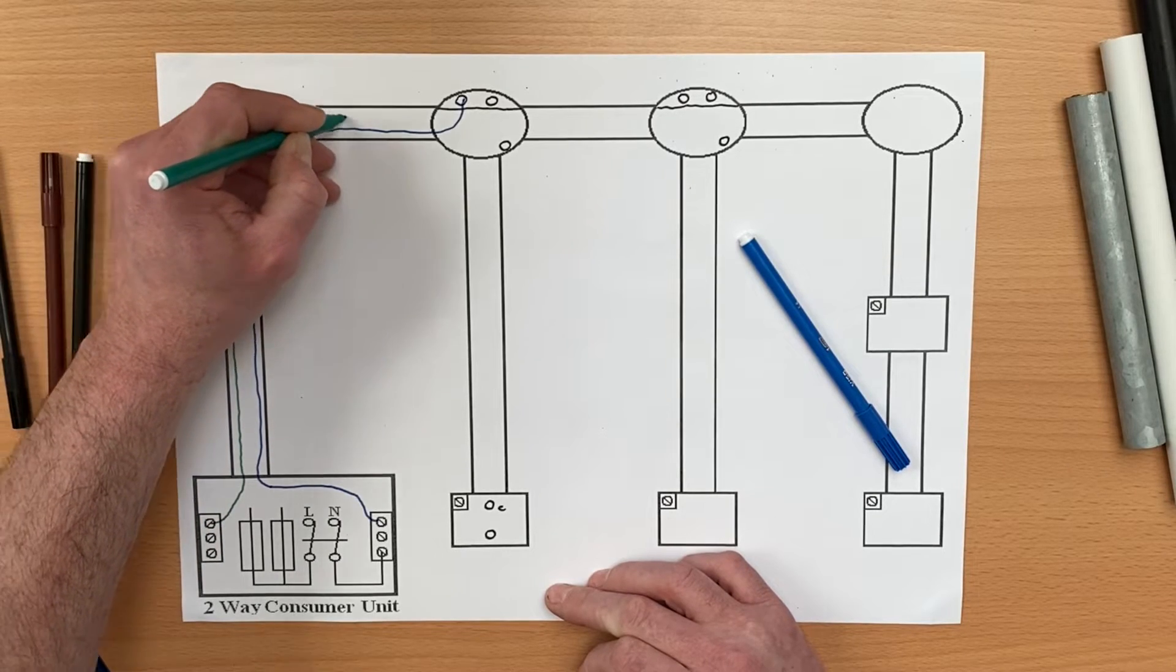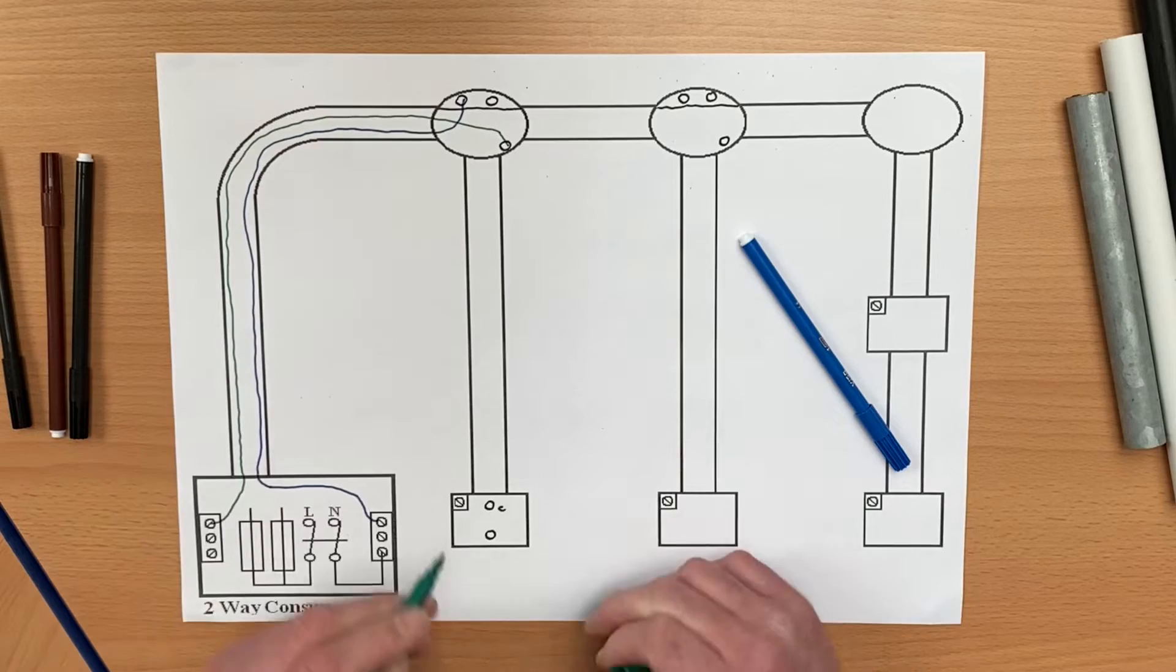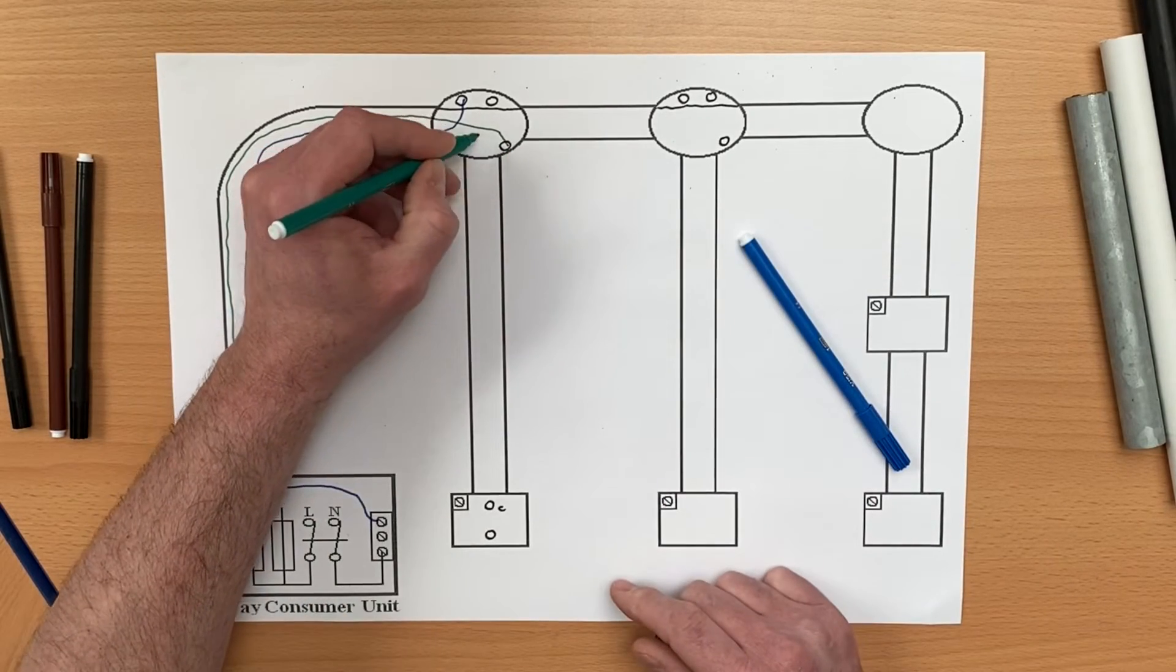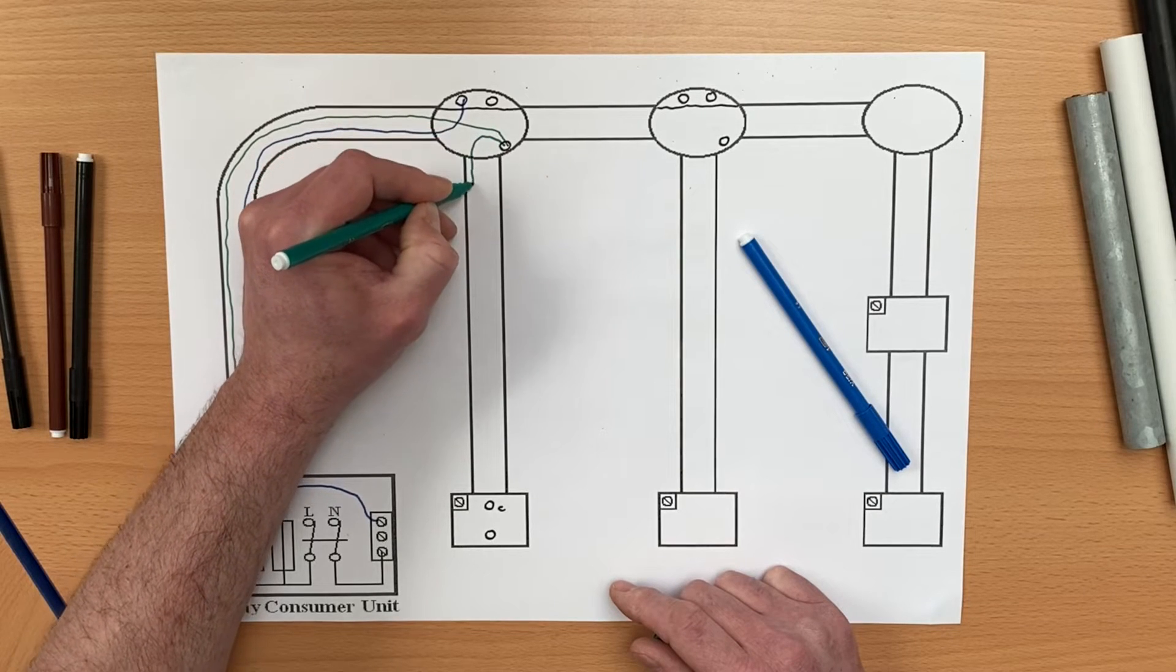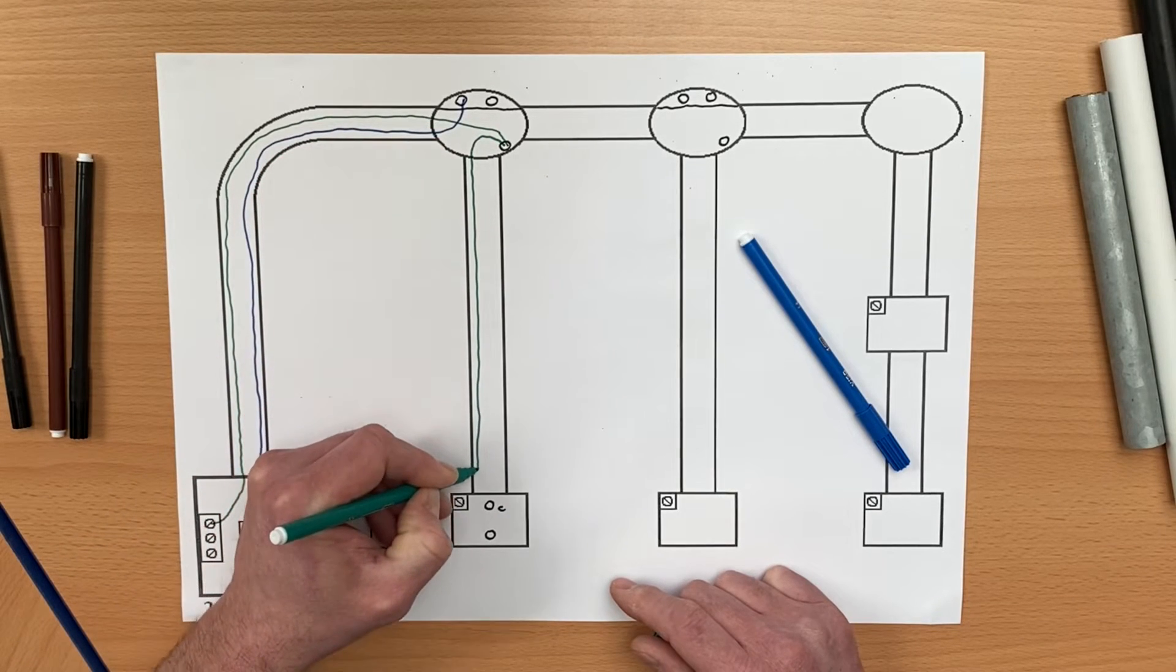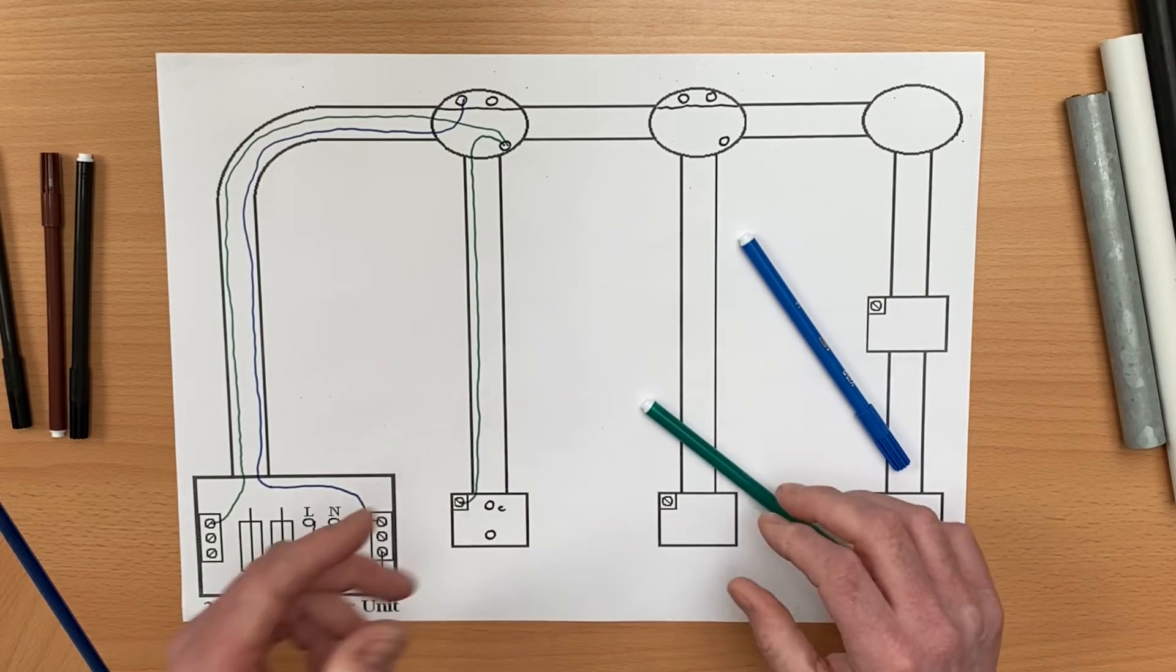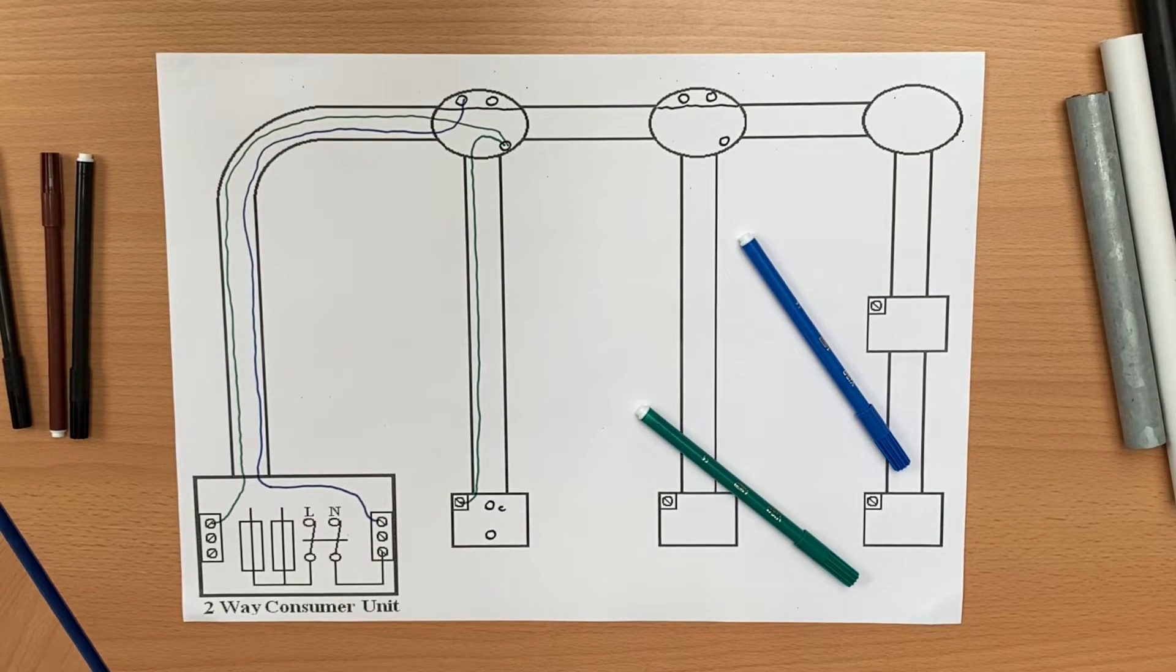Let's do the CPC next. We're going to come out of CPC, out the earth terminal in position number 1, and I'm going to drop that off first into my light fitting, in our case batten lamp holder, and then take a separate CPC down to the switch itself. So there we go, our CPCs have gone round.